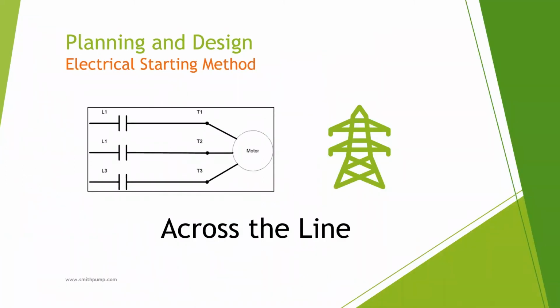And I want to quickly cover 3 options for starting a pump. The first and most common is across the line. Line power is directly applied to the motor. You only get one speed, but it's the least expensive way to run a pump.